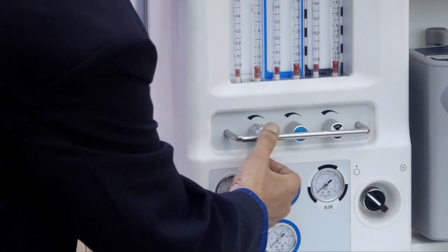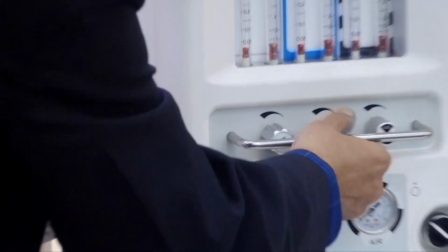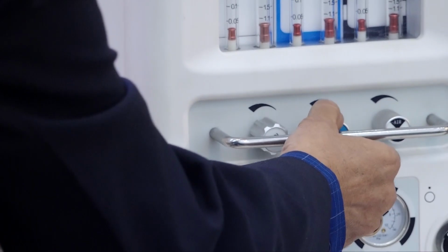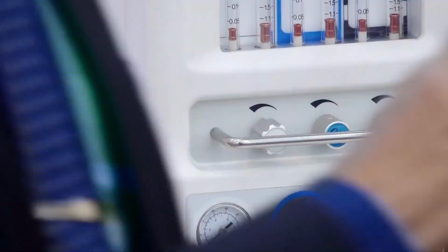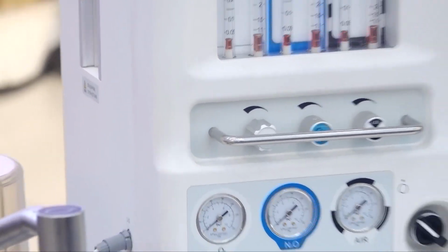So you can just see, if you concentrate here, can you see? So I'll just go back again. Can you see the rotation of oxygen also? I am actually rotating nitrous oxide. So you do that. If you are asked what kind of proportionating device is there in your workstation, just try to open nitrous oxide. If the oxygen flow control knob also starts moving, then it is Link 25. If it is not there, then it is SORC, sensitive oxygen ratio control.